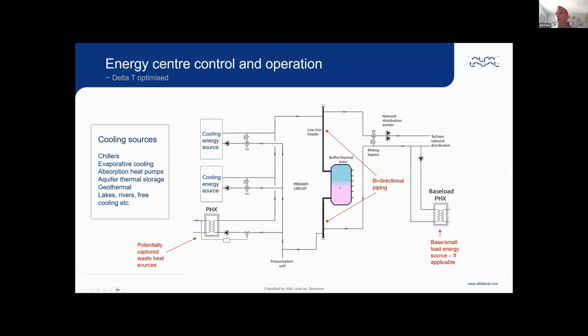And you can monitor where that stratification layer is in that thermal store by using thermal probes in the inside of the store, so you know its location, but crucially, you also know its direction of travel. So why will it change? Well, think about it. If this stratification layer is moving up in the vessel, it means you're using your thermal store, your store of cool water, on the system. So that means that your demand is greater than your output from all your cooling sources, because you're augmenting the cooling from the thermal store.